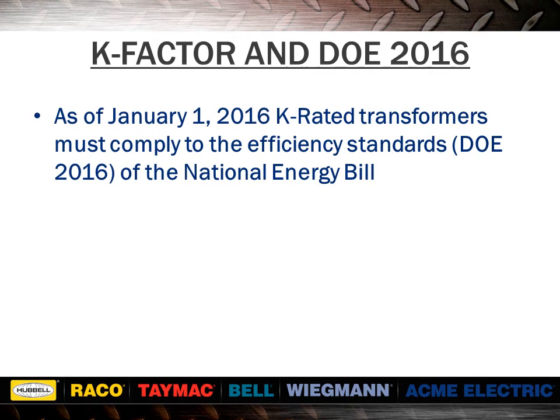As of January 1, 2016, k-rated transformers must comply with the Efficiency Standards DOE 2016 of the National Energy Bill. They are only required to comply with a connected load condition of k-1, meaning no harmonics.